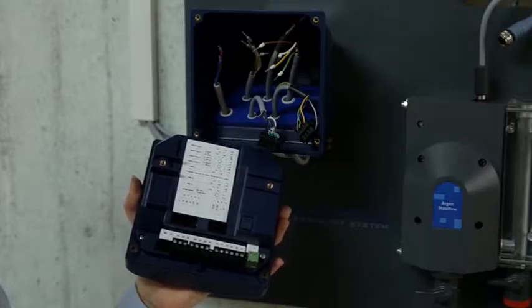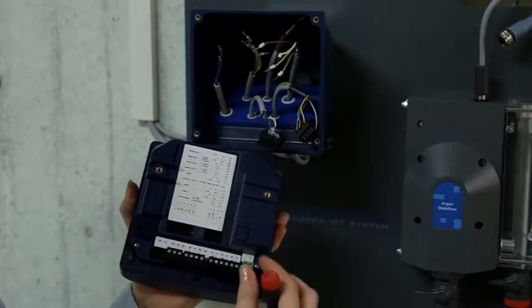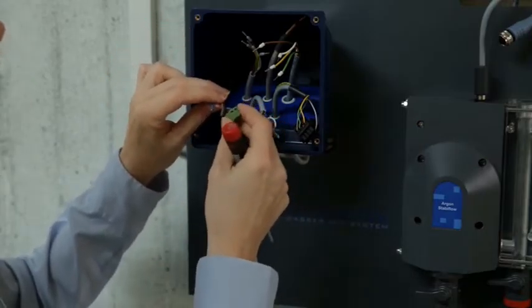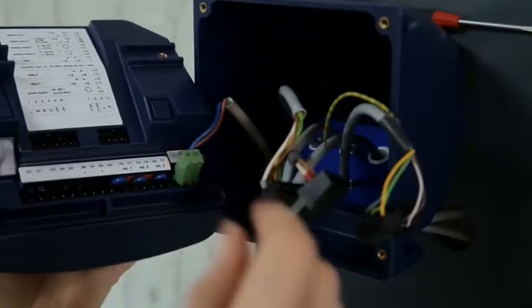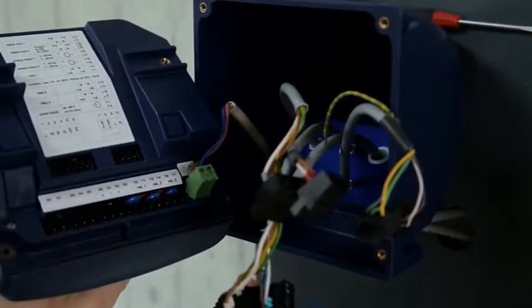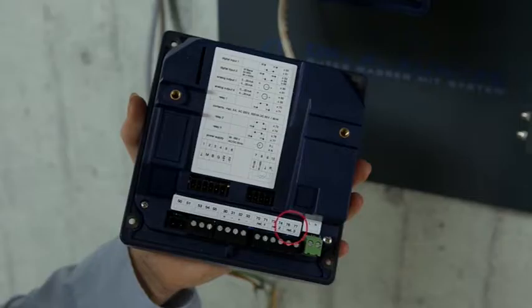Connect cables and terminals according to the connection diagram. Take out the terminals for cable connection. Connect the power supply to the green terminals marked L and N. Then we connect the alarm to terminals 76 and 77.